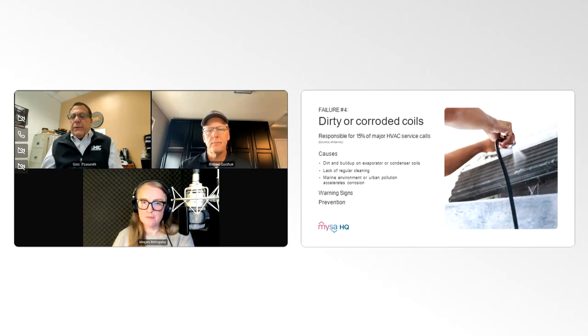If you have a restaurant, fast food facilities like that, a lot of times the condensing units might be on top of the walk-in coolers and freezers, which would be above a ceiling. Those coils tend to get dirtier a lot quicker. So one of the recommendations we make is that on a quarterly visit, the coils are cleaned in those situations. Depending on how busy a facility is, it might require more visits or cleaning. Rooftops, generally we see, need to be cleaned once, if not twice, a year, properly, based on the equipment type. That's about all I got on that one.